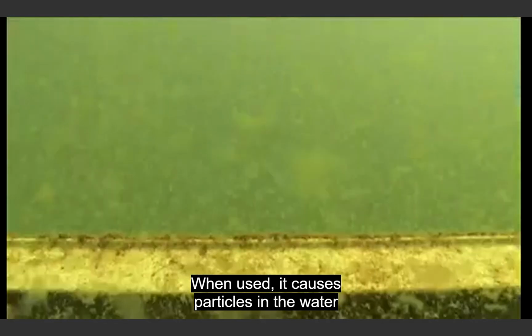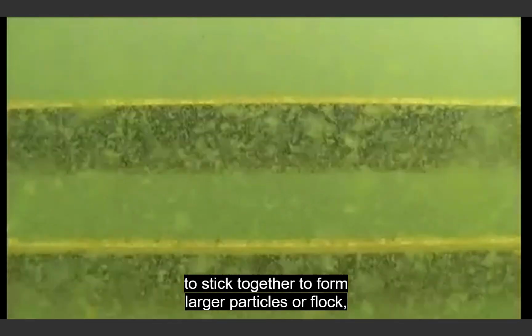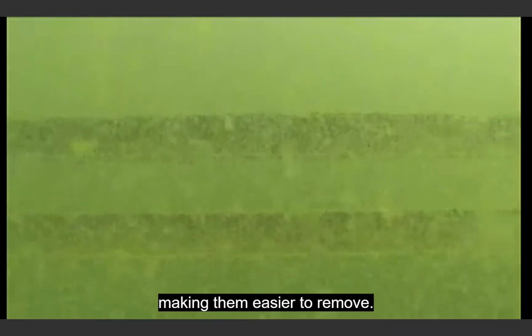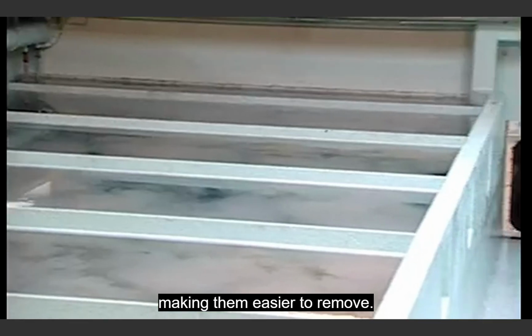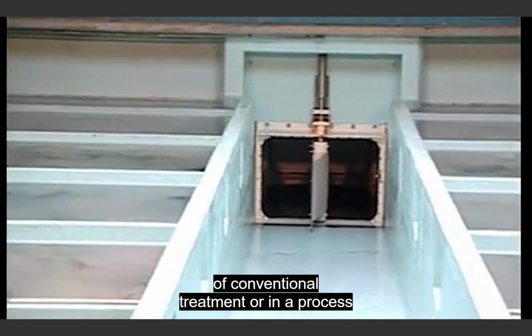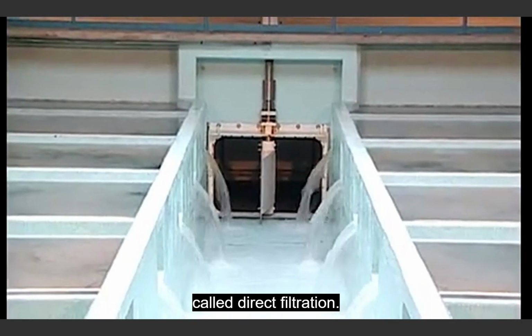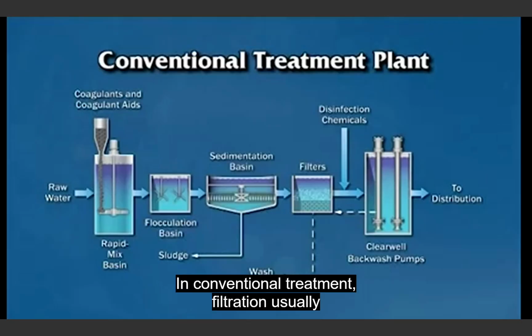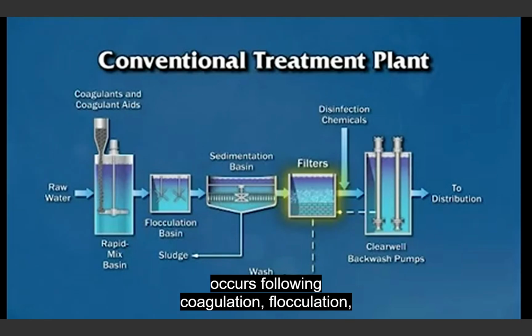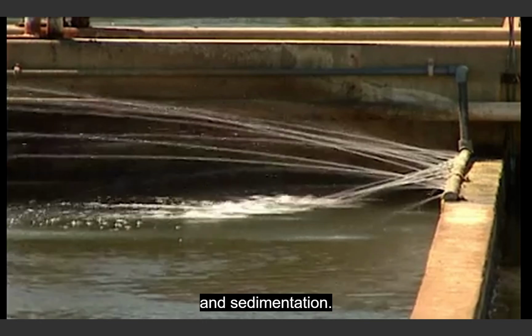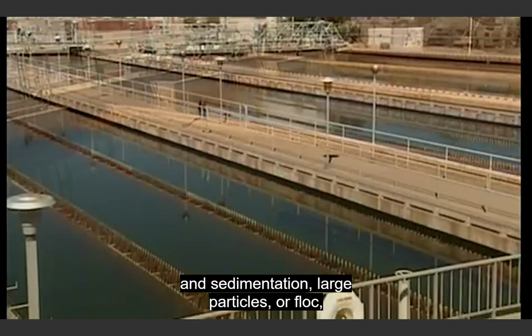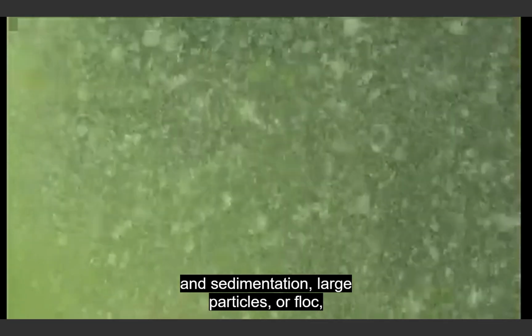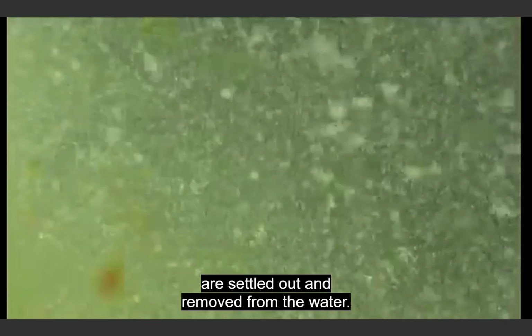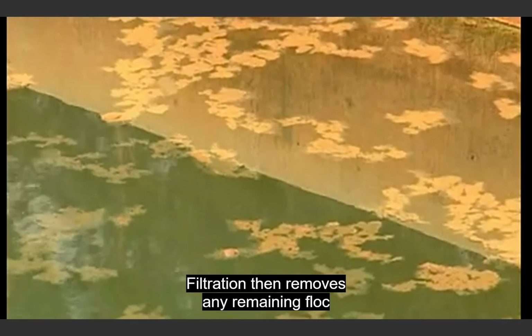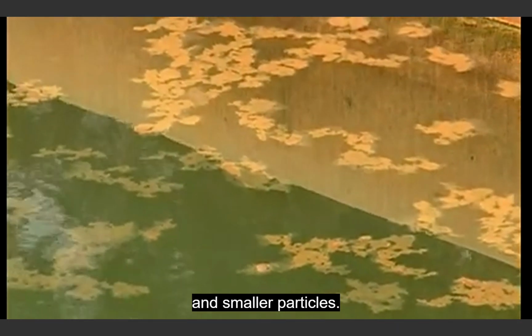When used, it causes particles in the water to stick together to form larger particles, or floc, making them easier to remove. Filtration can be used either as a part of conventional treatment or in a process called direct filtration. In conventional treatment, filtration usually occurs following coagulation, flocculation, and sedimentation. During coagulation, flocculation, and sedimentation, large particles or floc are settled out and removed from the water. Filtration then removes any remaining floc and smaller particles.